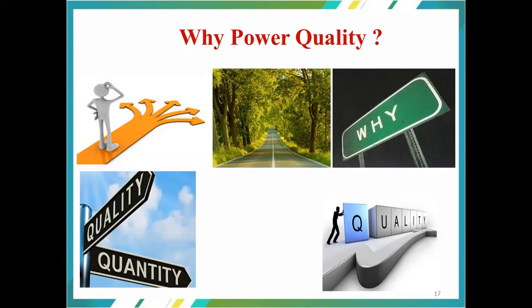So assume that all this power, that is the 16,000 megawatts or the 1,80,000 to 2 lakh megawatts, is going to get transferred from the generating station all along to the consumer end. While transferring the power from a particular point to the consumer end, we are going to process it in terms of converters or inverters, or process it through the transformers, or through the transmission lines. So all along the way, we are supposed to maintain both quantity as well as quality among the 5 regions of our grid.